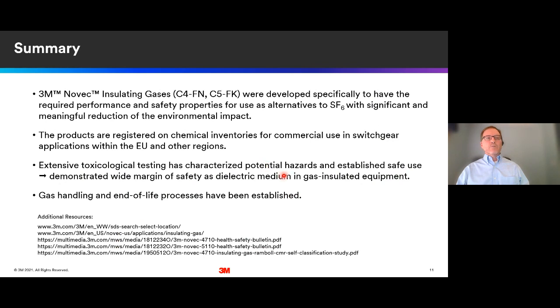So in summary, on the new alternative gases that are being installed, the Novec insulating gases, C4-nitrile and C5-ketone, they were developed specifically to have the required performance and safety properties for use as an alternative to SF6 and provide a significant and really meaningful reduction of the environmental impact. As we showed, over the life of the equipment and certainly over a GWP calculation, it can be up to 99.9% reduction in the greenhouse gas emissions.